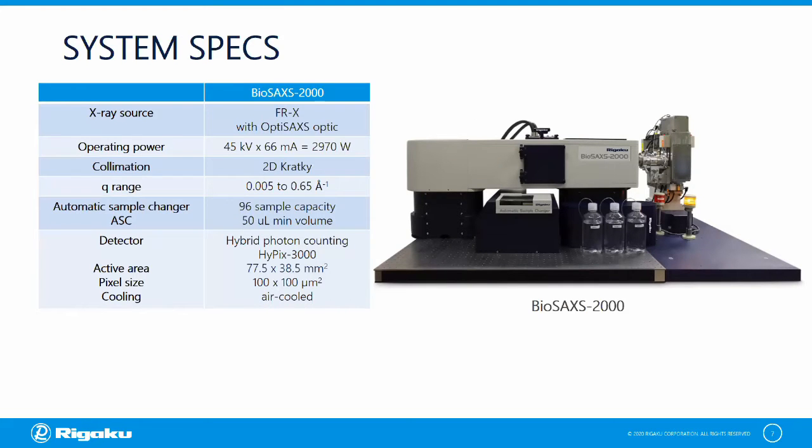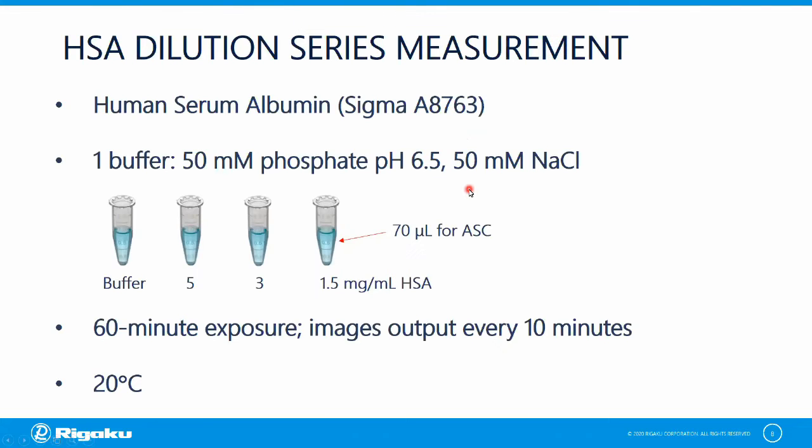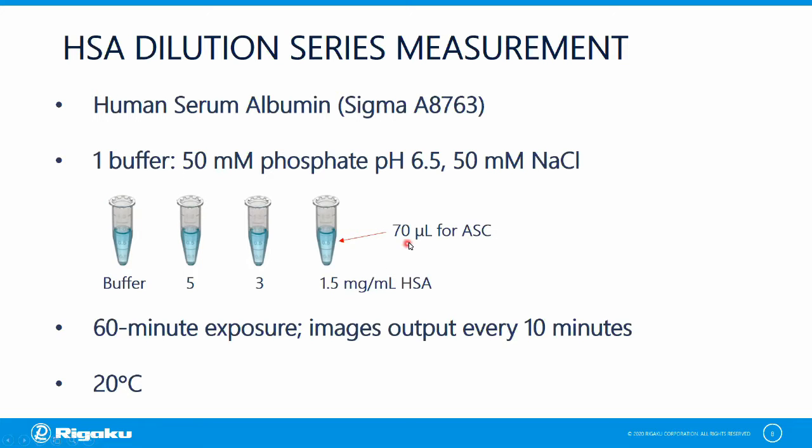The data that I'll show you today were collected on a BioSAXS 2000 on an FRX X-ray source. Our setup included a Rigaku HyPix 3000 hybrid photon counting detector and an automatic sample changer. I collected data on human serum albumin, or HSA, from Sigma. The protein powder was reconstituted in a phosphate buffer, then centrifuged, and then serially diluted to 5, 3, and 1.5 mg per ml. This is a simple dilution series, single buffer, three concentrations. 70 microliters of each were loaded into the automatic sample changer, and 60-minute SAXS exposures were recorded, and the detector output an image every 10 minutes for inspection. The data collection temperature was 20 degrees Celsius.